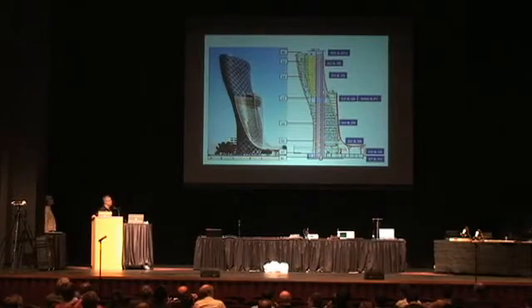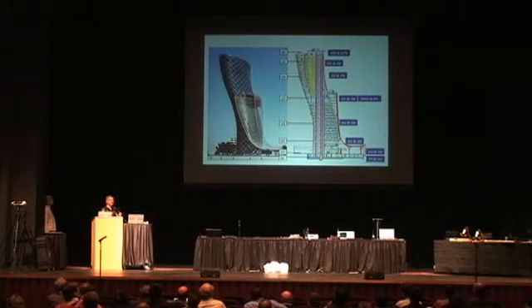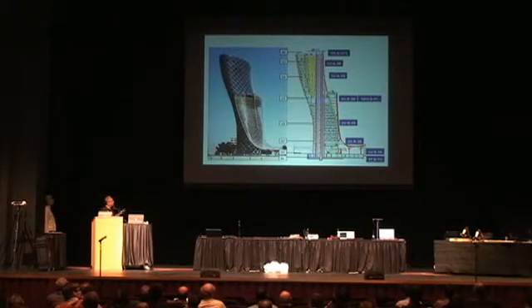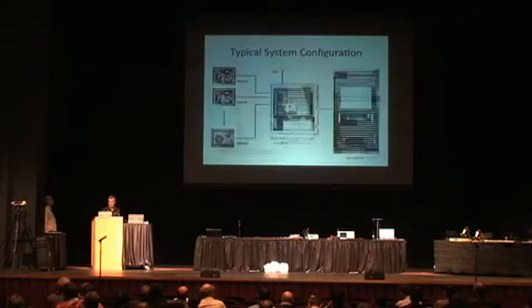This slide here shows the distribution of the sensors. We had obviously the wind sensor and GPS on top of the tower, and we go from one of the basements all the way up, instrumenting different levels, typical floor plans. As you can see, this structure represented a particular challenge because at the same time that it's leaning, I don't have a plan view here, also the plan is rotating. So it was quite a challenge to define sensor orientations and so on.